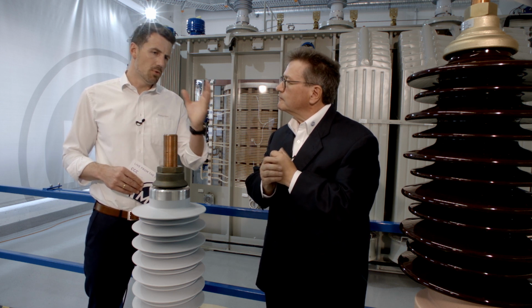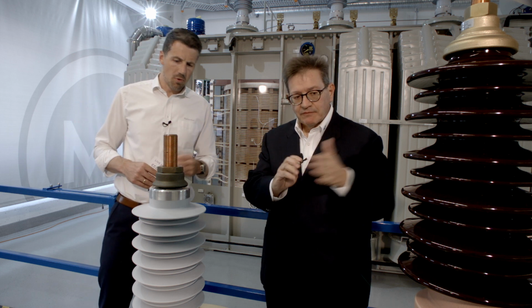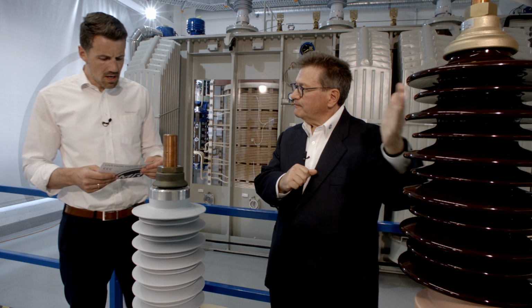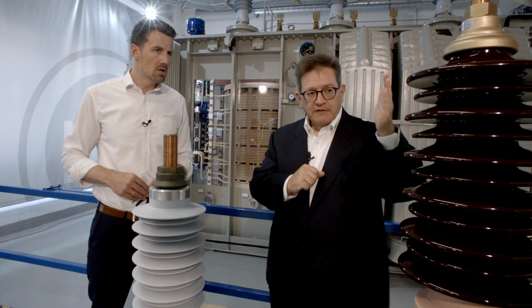So we see the porcelain bushings on the left-hand side, the polymeric bushing, the silicone shielded one, here. What types do we see here specially? This is a 52 kV, 1,250 amps, porcelain insulator bushing. This represents the historical application, because porcelain has been used for more than a century in transformer applications. Porcelain insulator is perfect. It's a very nice insulation material, very good as far as compression set and mechanical properties are concerned.